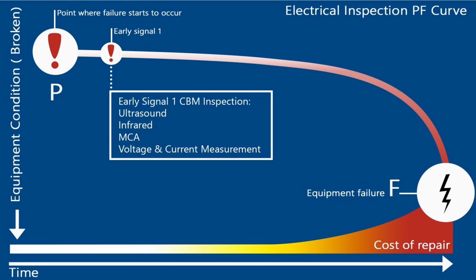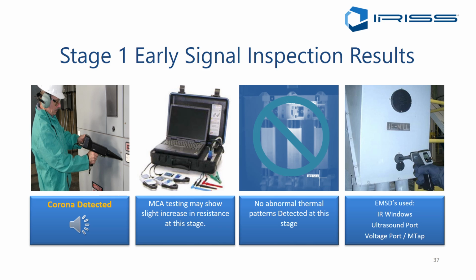So let's look at an electrical system. We've got a point of potential failure, and we come up to the early signal stage where we use ultrasound, infrared, and motor current analysis. Looking at the curves, the motor current analysis might show a slight increase at this stage.